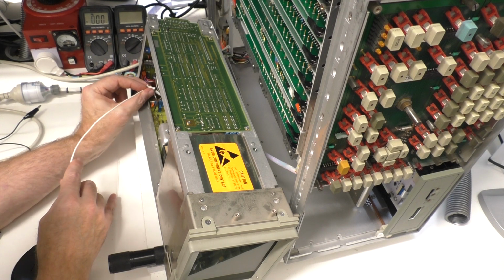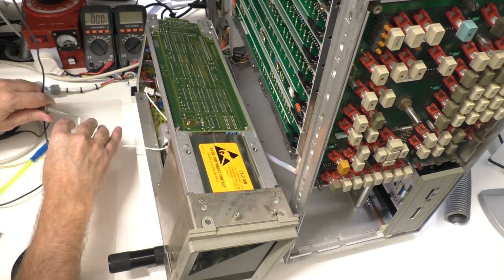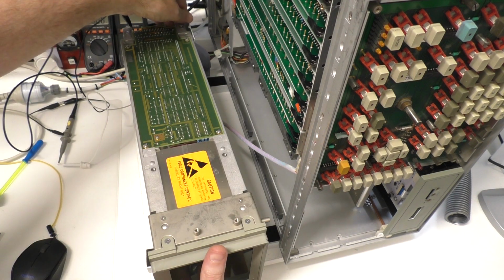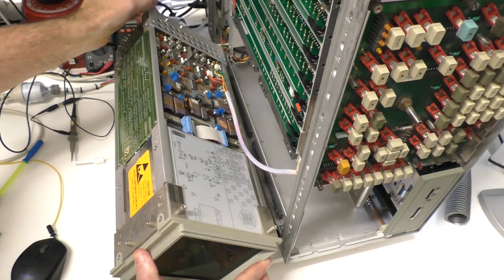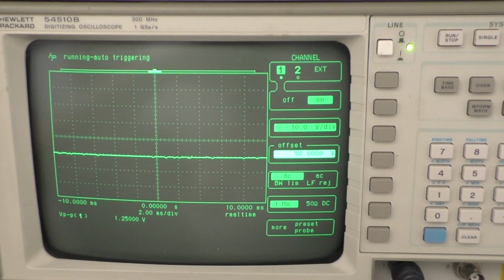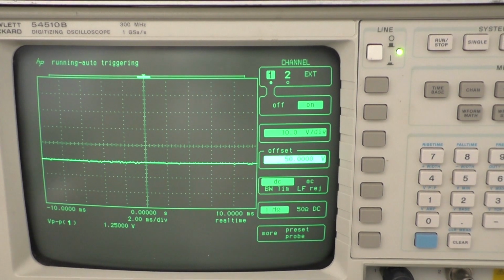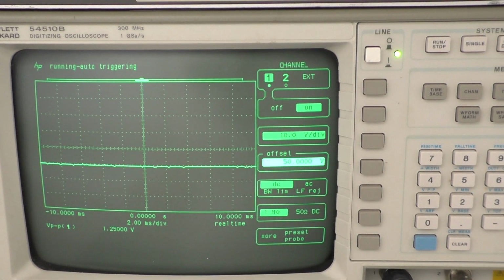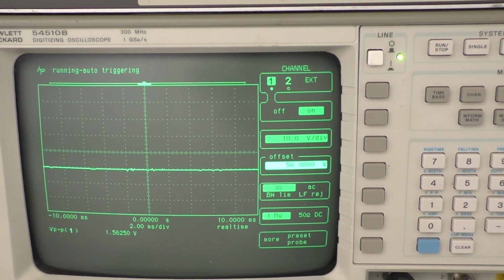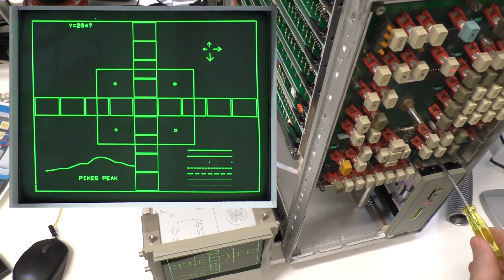The other end connect to the scope probe. Attach the probe ground to chassis. Put the display back on its bottom. Ensure the probe is on 10:1. Set the scope to 2 milliseconds per division, 10 volts per division. Power up. Turn the intensity all the way down.